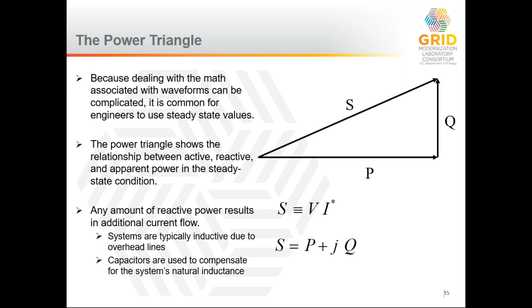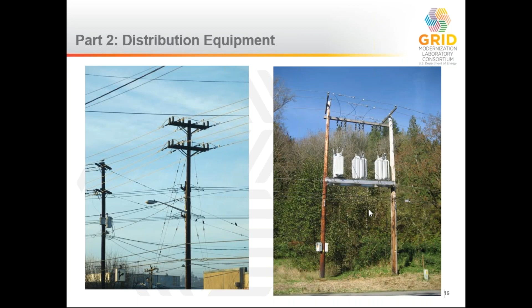And that brings us to the second part, where we're going to go in and start looking at some of the key pieces of equipment in electric distribution systems. Next slide, please. The most important part of a distribution system starts with the distribution substation. For most distribution circuits, this is going to be the source of power that steps down power from either the transmission or sub-transmission system. So something on the order of 100 to 200,000 volts, possibly up to 230 or 500. And it will step it down with a substation transformer to voltages that are typically less than 50,000 volts.